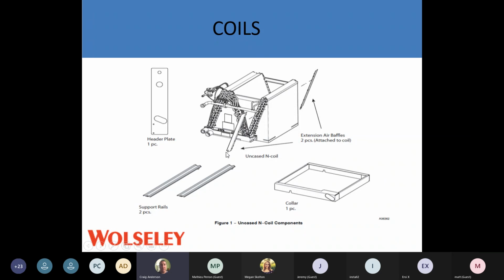So if you'll notice in the bottom part of this picture is a plate. This plate is actually attached to the coil when you take it out of the box. Take that plate off the coil. That is your template. When you take it off the coil, you can turn it upside down and sit the coil on top of it inside the plenum, or you can keep it the same way that you took it off the coil and install it that way. So once you install that plate and screw it in with your angles and everything, as long as that whole opening is open in that plate, then you're fine when you sit your A coil on it. So it's a great template, especially if you're using channels.